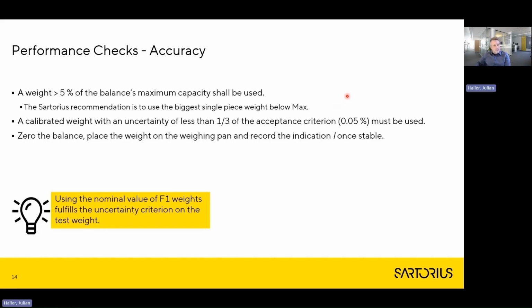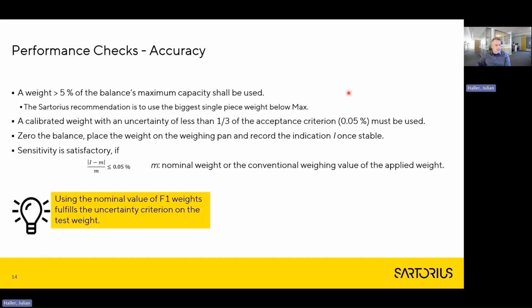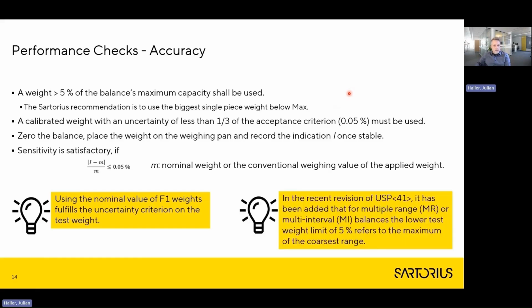For the test itself, zero the balance, place the weight on the weighing pan, and record the indication once it is stable. The sensitivity is satisfactory if the difference between the indication and the weight divided by the weight is less than or equal to 0.05%. Note that in the recent revision of USP Chapter 41, it has been added that for multiple range and multi-interval balances, this lower test limit of 5% refers to the maximum of the coarsest range, so to the overall maximum capacity.